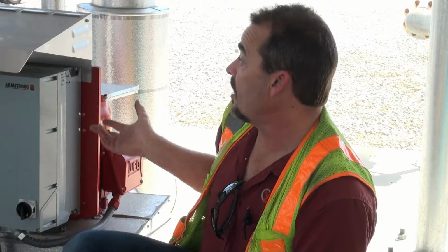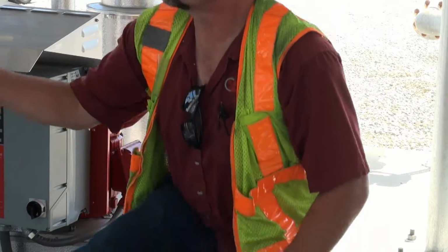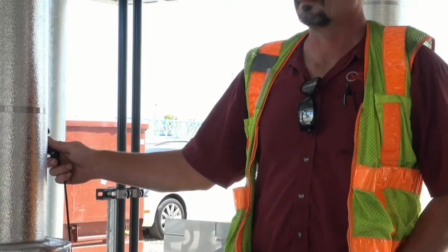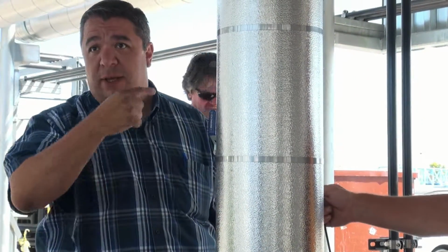As far as the pumps go, we talked about the pump standard. There's no difference in the pumps with the ones we talked about. They're close coupled, vertical inlines, no greasing, no lubing. There's no difference in that small pump. I thought there was a difference, but there isn't. It's exactly the same kind of pump. It has the same water line that goes from the pump back to the mechanical seal to keep water in it. So there's no difference in the pumps, obviously just the size of the mechanical seals are different, but pump functionality, there's no difference in either pump.